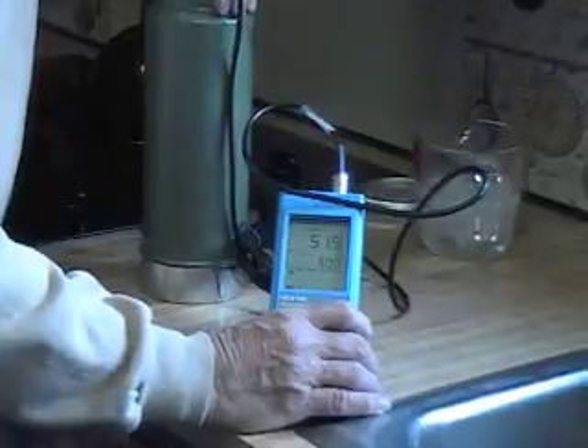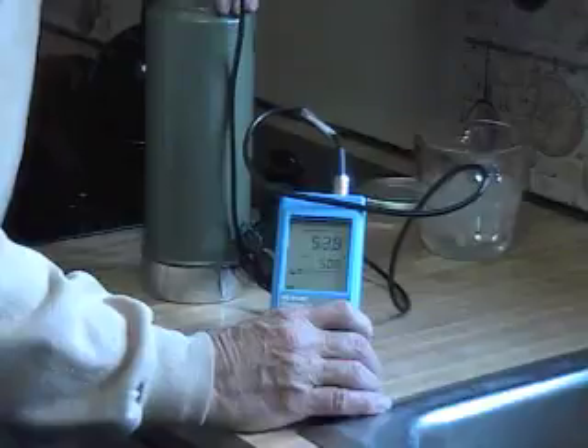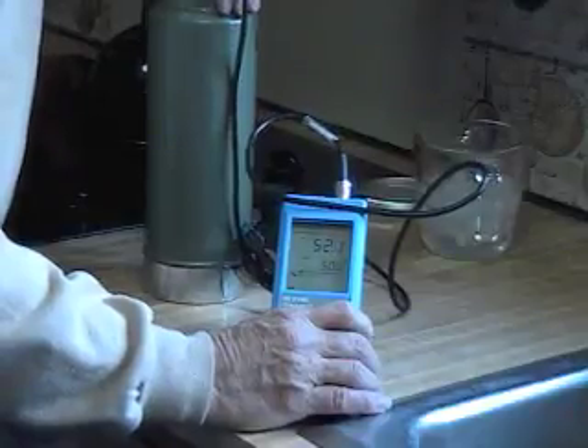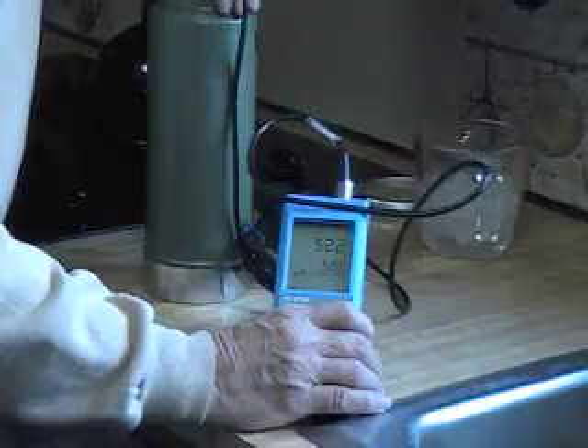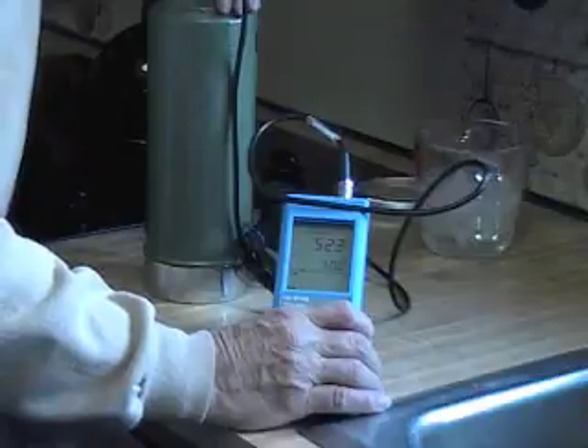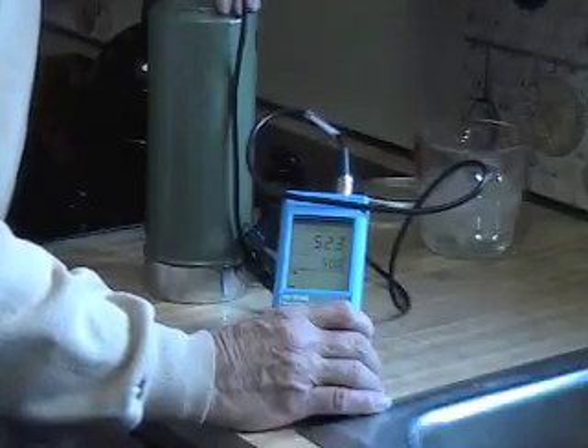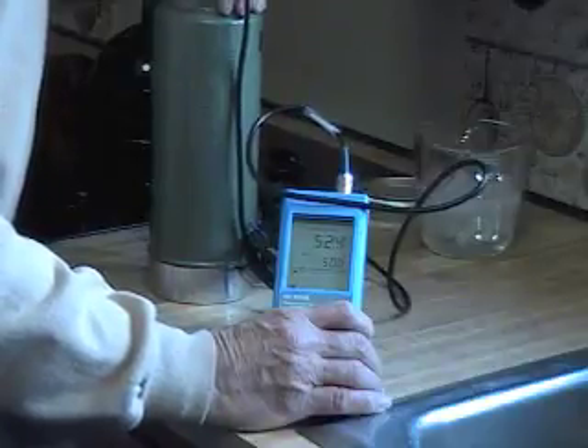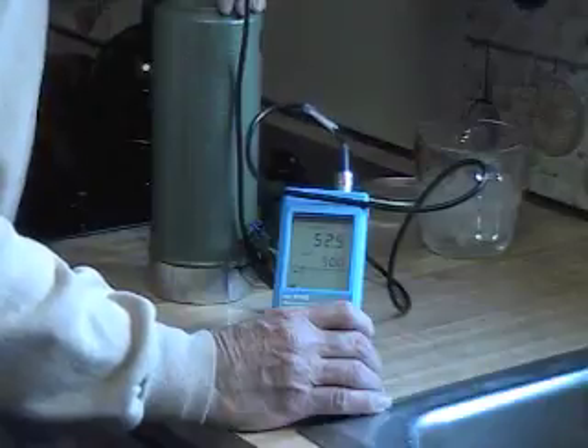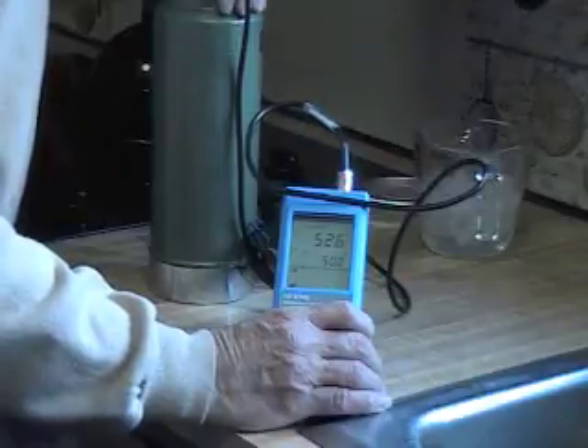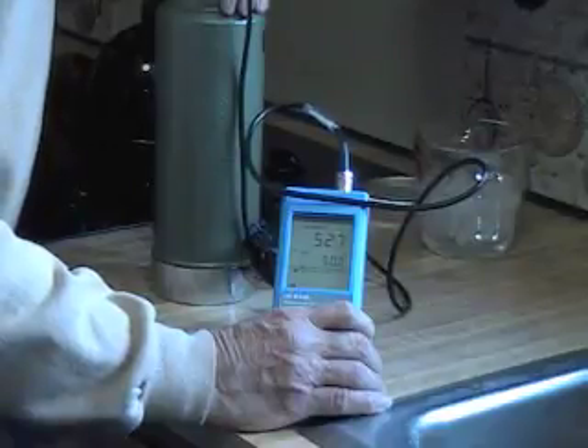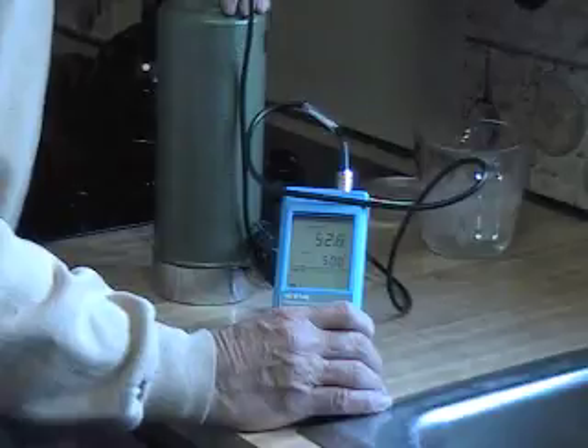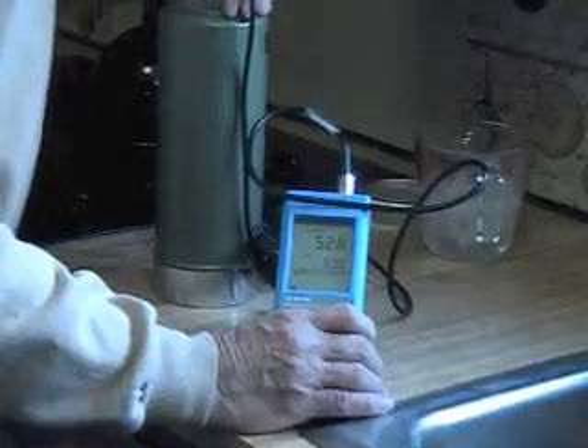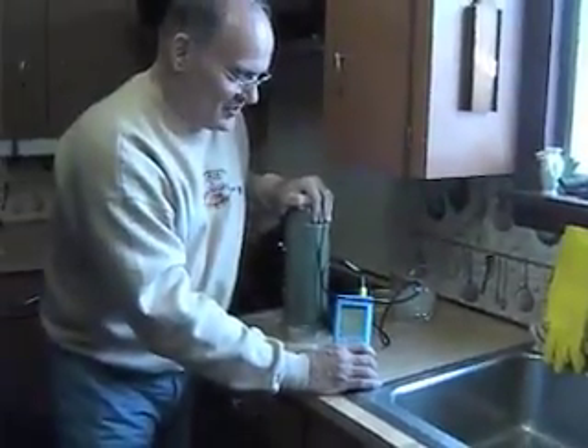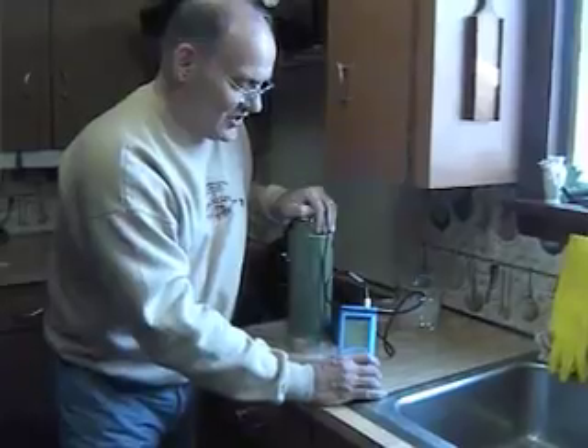And you can see now we've had the probe in this water for a while, and you can see the water temp is above 50. And I think if it's in water too much above 50 degrees, and I don't know what that number is to tell you, but I've seen it happen where if you stick it in water that's significantly higher than 50 degrees, you're going to get some kind of an error statement flashing, because really the instrument's designed to handle that 0 to 50 degree range. Now once this thing settles down, we'll just wait a few more minutes, but once it settles on the actual temperature, I'll confirm that. I'm just going to wait and let it settle. You can see it's still changing.